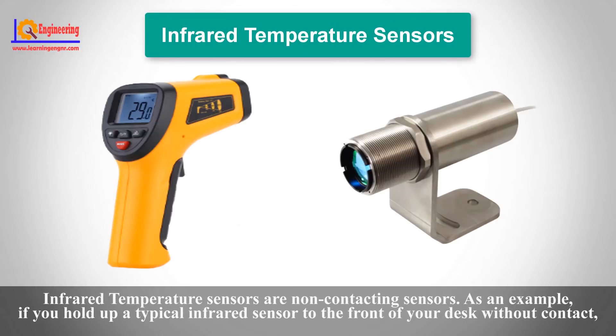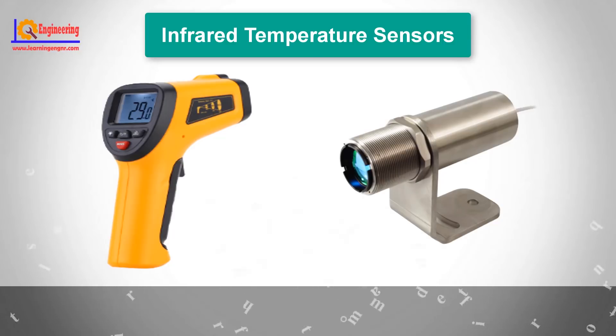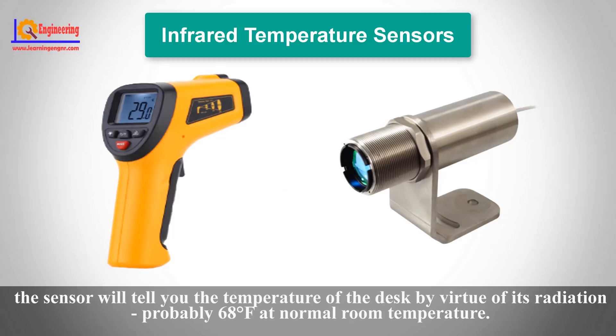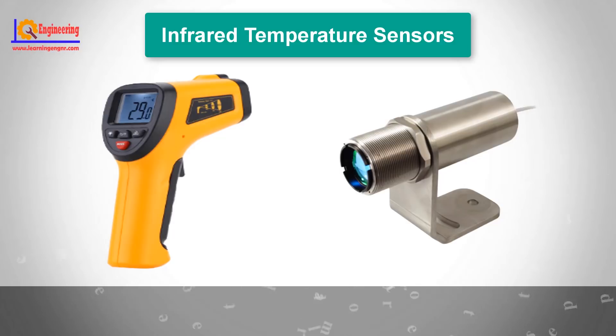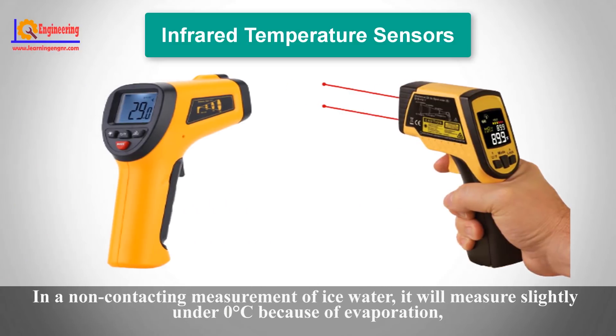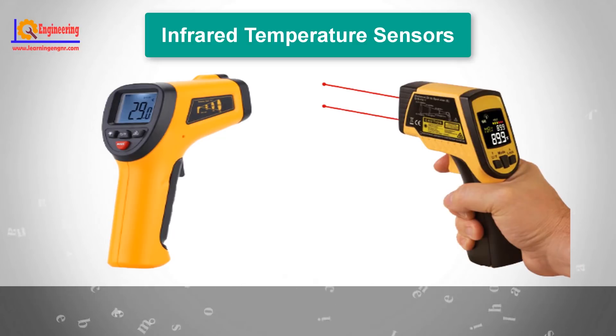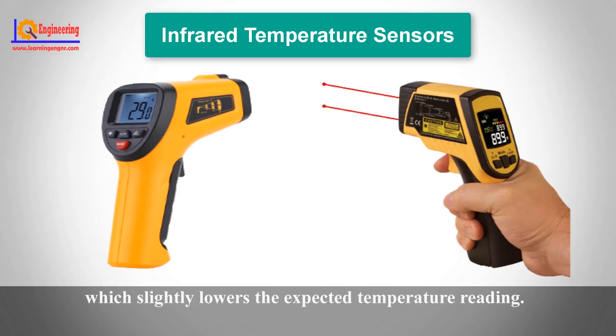Infrared temperature sensors are non-contacting sensors. For example, if you hold a typical infrared sensor in front of a surface without contact, the sensor will tell you the temperature of that surface by virtue of its radiation — probably 68 degrees Fahrenheit at normal room temperature. In a non-contacting measurement of ice water, it will measure slightly under 0 degrees centigrade because of evaporation, which slightly lowers the expected temperature reading.